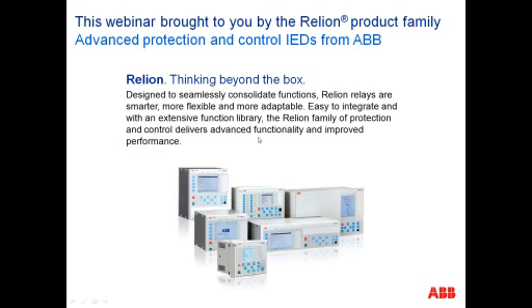It's usually some type of flashover of an insulator or something like that due to contamination, or a momentary breakdown in insulation during a lightning storm, or a tree bumping into a line, or something like that. But that's why we strive for high speed in some cases, or reasonably high speed. But more than that, you want to try to clear it as fast as possible. I'm not sure exactly what the guy's questioning, but you trip what you can directly, that's the reason we have zone 1. We determine a fault, we trip fast, and if you have to use the communication channel, then you use the communication channel to get simultaneous tripping.